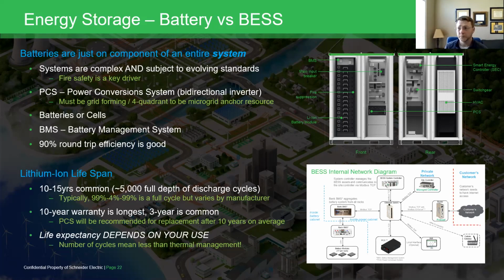This is incredibly important. If you want to use that resource as the anchor resource for your microgrid, you need to make sure it's coming with the right PCS. It needs to be bidirectional and a grid forming true 4-quadrant inverter. Those are some buzzwords to look out for when you're reading about batteries. If they have those applications, that battery can be used as an anchor resource.